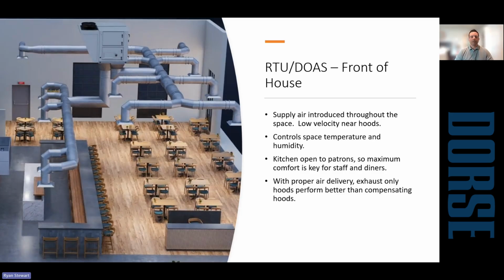And from a hood performance standpoint, the UL testing that they've done achieved the lowest airflow with non-compensating hoods, just standard exhaust only, with all the makeup air being introduced away from the hood at low velocity. That's the best outcome as far as lowest air volume for the hood. So you get some additional benefit from lower exhaust airflows with this approach.